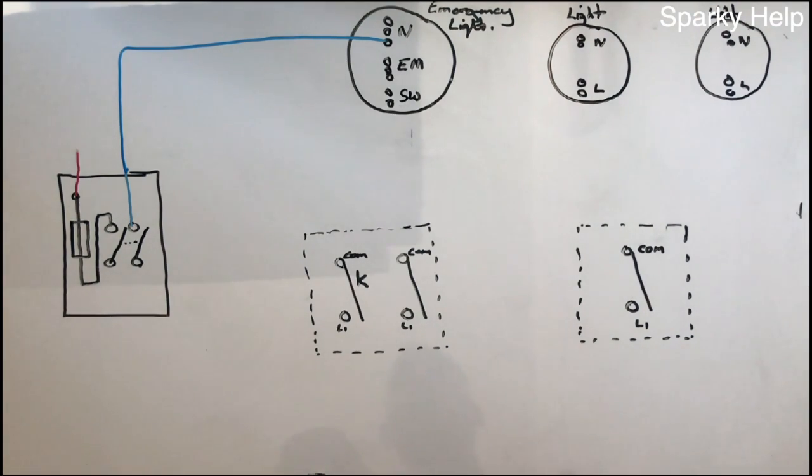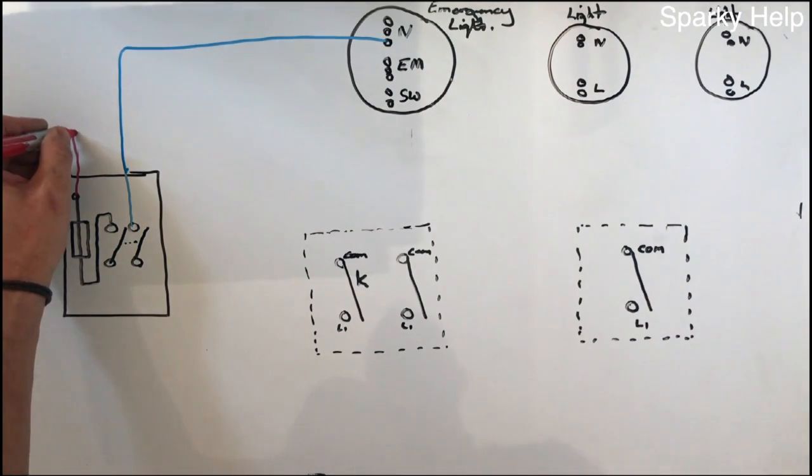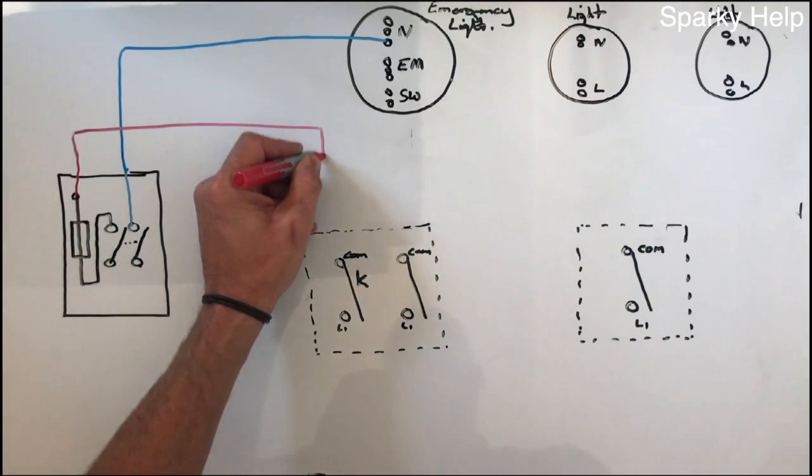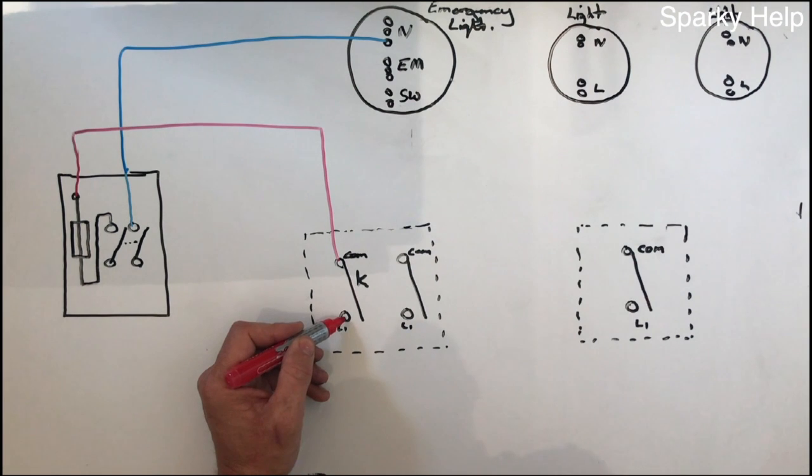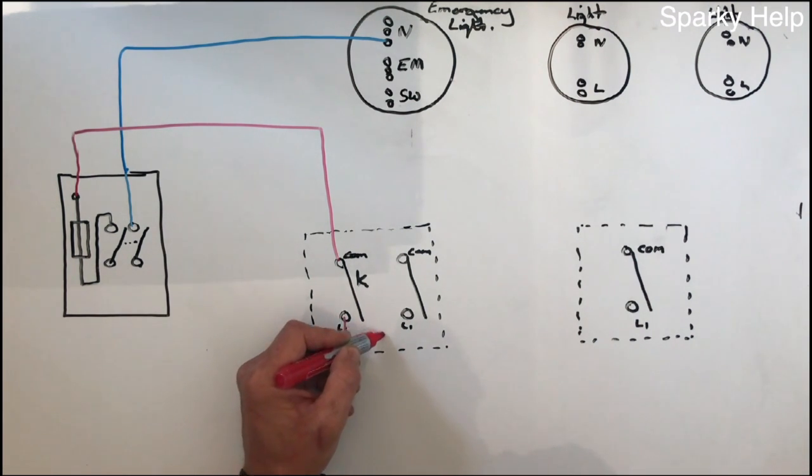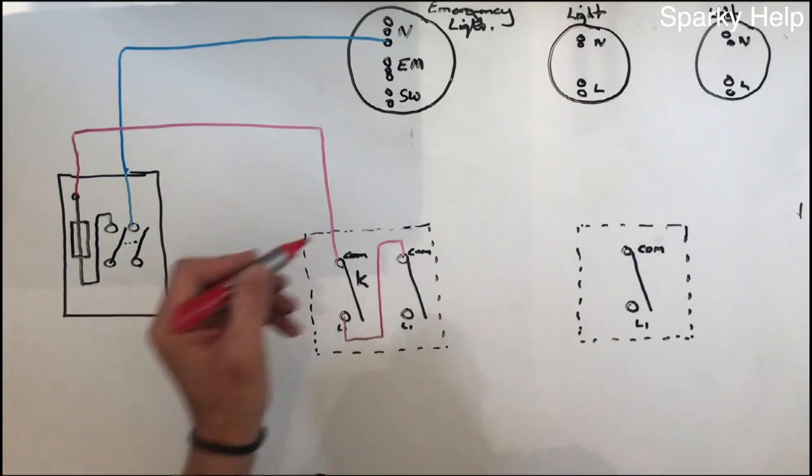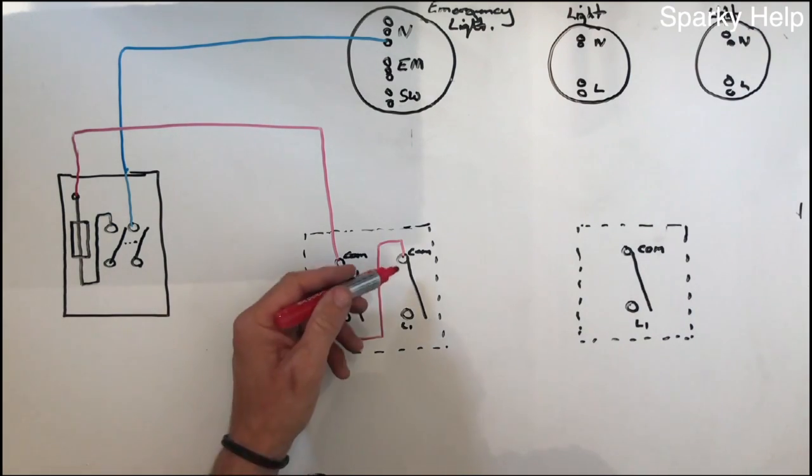So, how do we wire this one? Well, the feed will come out, doesn't need to go up here, because we don't need it up there, so what we do is we take it into the key switch first. So in the top of the key switch, this then will link out, and go into the top of the common.